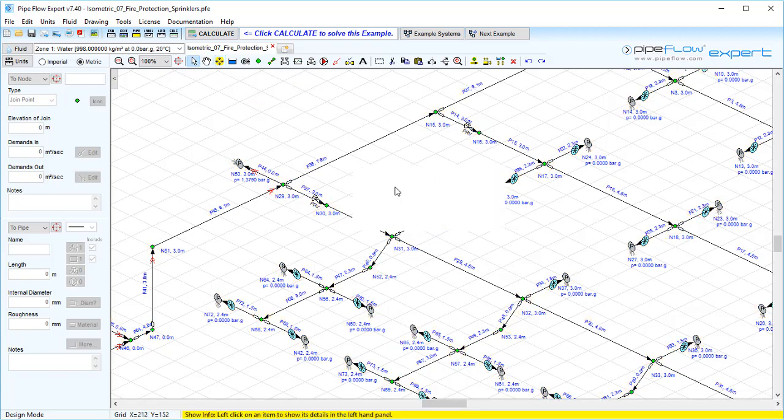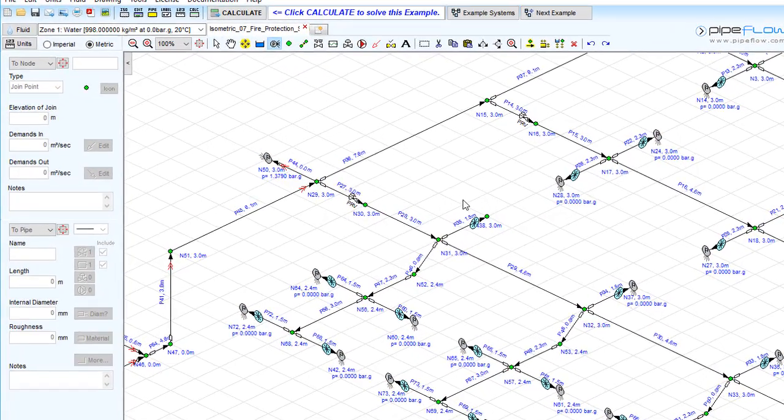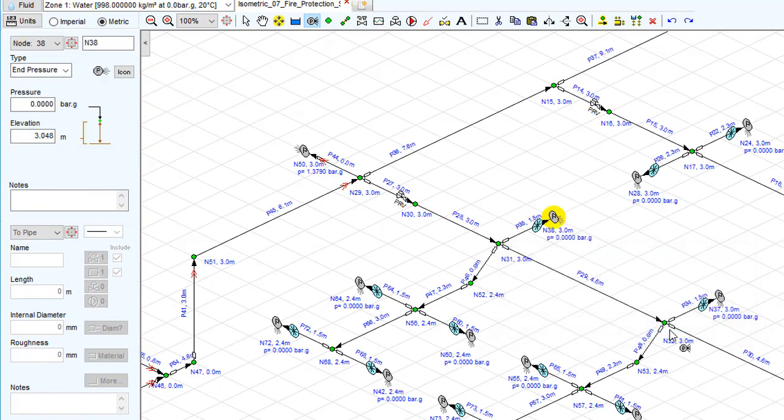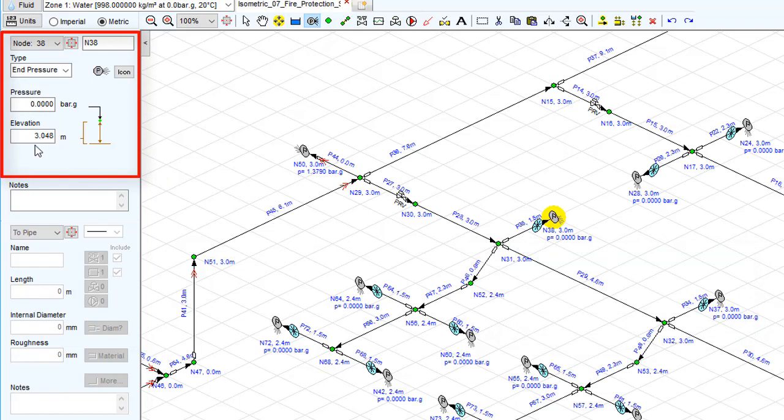To complete the model for discharge to atmosphere, we need to add an end pressure node set to zero bar gauge. Alternatively, if the spray discharged to a pressurized tank, then the end pressure node should be set to the pressure in the tank.